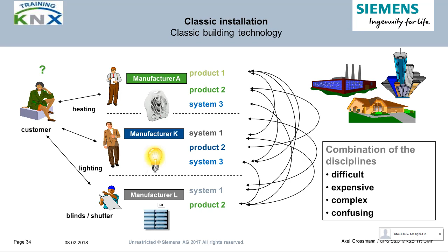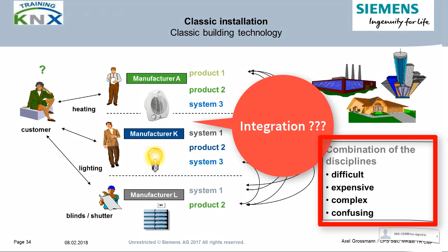Disadvantages of classic installation. This image shall clarify the problems inherent in conventional solutions. For all disciplines you will find individual solutions, for example a blind control system from a manufacturer of shading technology, a heating control system from a manufacturer of heaters, and something for lighting automation from lighting manufacturers. But if you try to synchronize all disciplines into one single management system, as is sensible nowadays, you won't succeed easily with such individual solutions. If you have to do it nevertheless, it becomes complicated, complex and expensive.